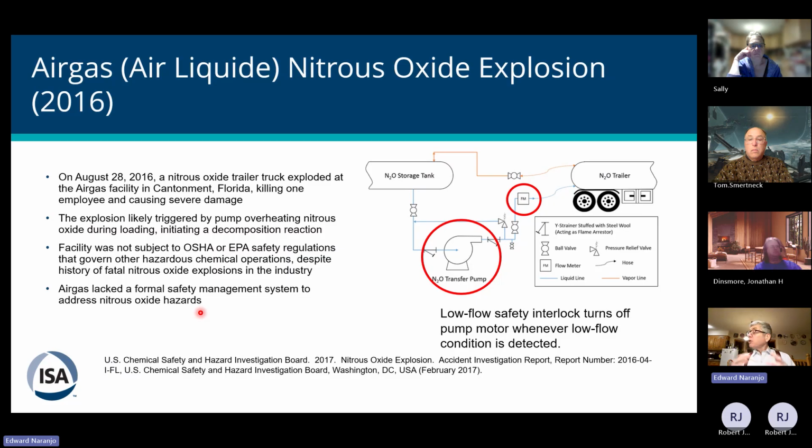And the second one that may surprise some of you is that even though the process safety management standard does not apply, there is an expectation from OSHA that companies are going to use standards, including, by the way, ISA 84, because that's a recognized and generally accepted good engineering practice, or RAGAGEP, as it's known, to try to manage and increase the safety standard of these types of facilities.